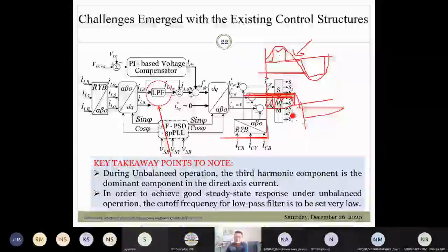Okay, this is your compensating command. These compensating currents will be processed through the hysteresis current controller, and that will generate the pulses for the IGBTs of the inverter.